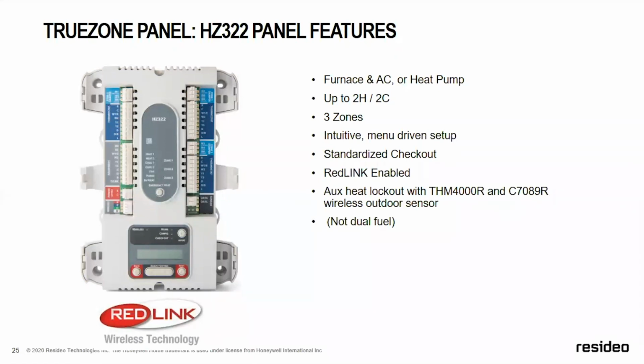It is RedLink enabled, which means it will do wireless thermostats. However, to do RedLink, you will need to install a THM4000R to operate anything wireless with RedLink. And with a C7089R, you can use wireless outdoor sensors. This panel does not do dual fuel.